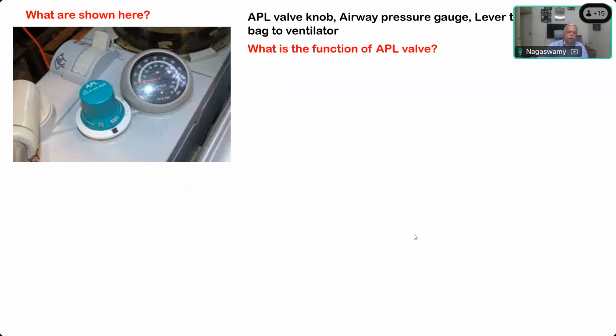What is the function of the APL valve? It helps in providing positive pressure ventilation during manual ventilation. And also it helps in venting out when the pressure inside the machine is high. Supposing the patient is breathing spontaneously, does this valve have any role? Yes, it provides PEEP, CPAP. PEEP during control, but CPAP during spontaneous ventilation.